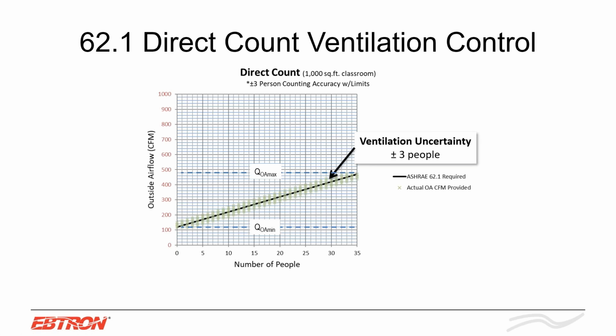And another area where you can even take this a step further is to directly count the people coming into the space. Now, sometimes this is known depending on building types. Sometimes you have a point of sale, you have turnstiles in arenas, you know the number of people coming into movie theaters. So you can stage your air handling unit to bring in the required amount of ventilation based on the population in the space. Now, what we make at EBTRON is a population counter. It's called the census counter, and that has an uncertainty of plus or minus 3 people. But if you look at it here in this simulation, it's way better than the CO2.